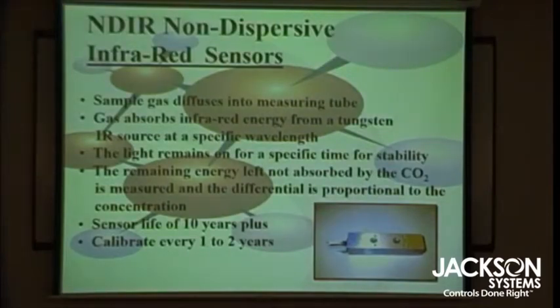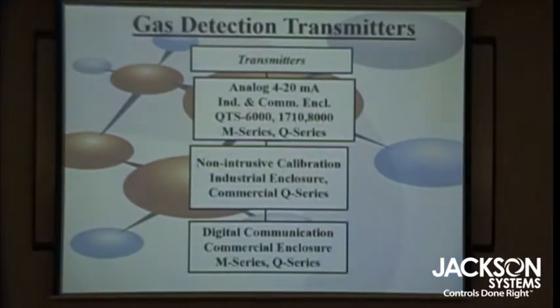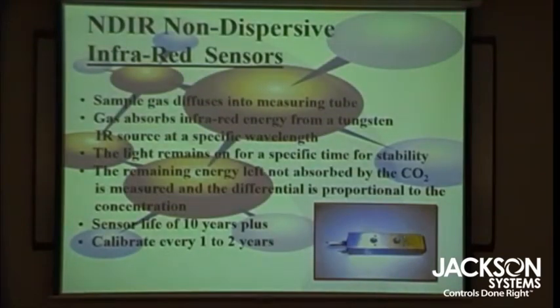But they were using catalytic sensors in the past and having to change them every 4 or 5 months because the sensors would wear out. If you need a job site visit there, Jackson Systems will help out. Okay, no problem. Check it out. So they installed electrochemical sensors. The payback was within a year. And you pay more for it, but you don't have the maintenance, and you check the calibration once a year. So you don't need all the extra personnel to do that. We also use infrared sensors for our refrigerant monitors, which I'll go into later.